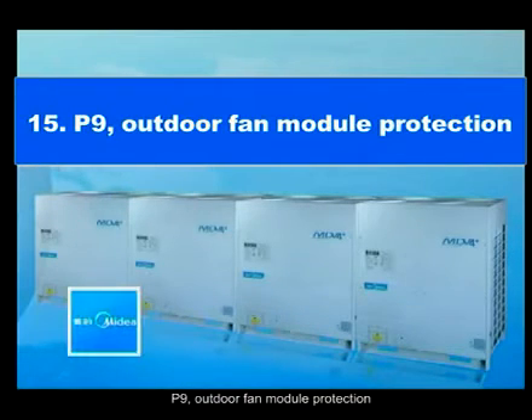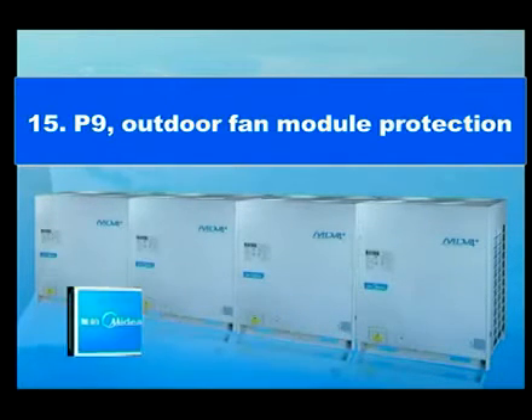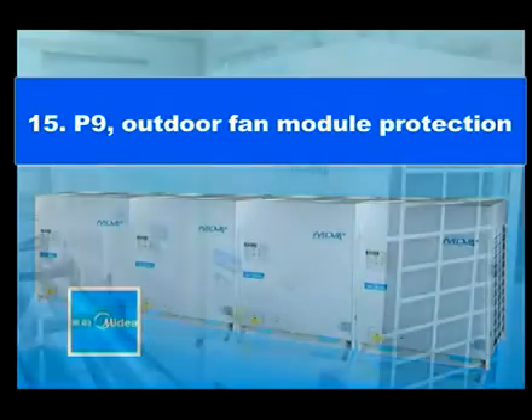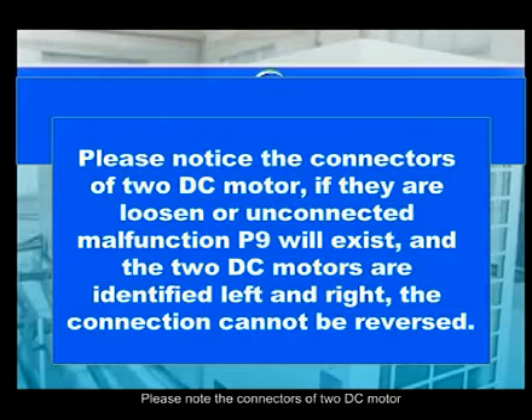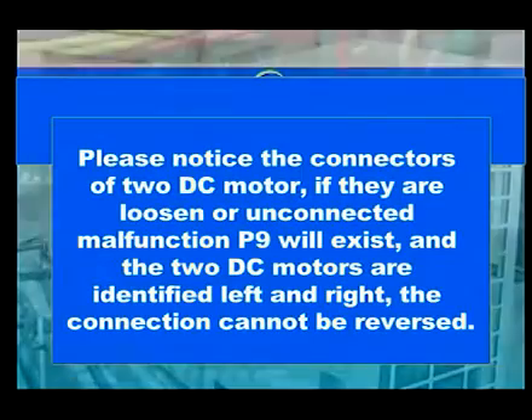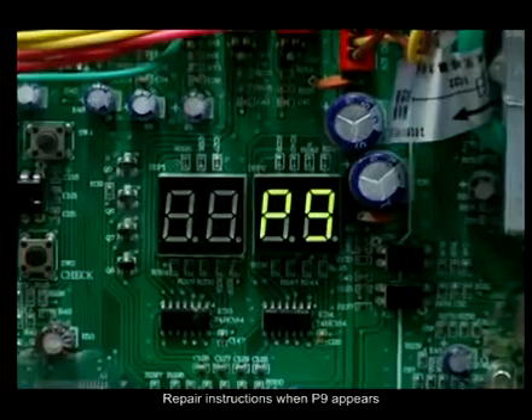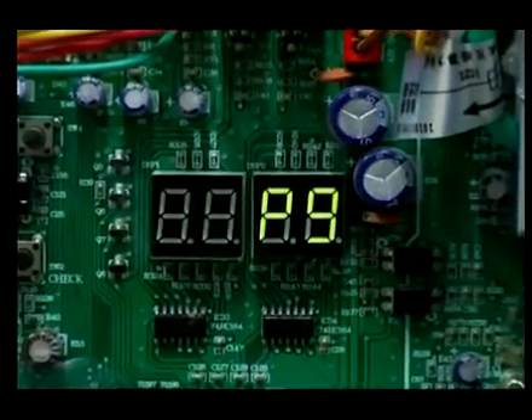P9. Outdoor fan module protection. Please note the connectors of the 2 DC motors. If they are loosened or unconnected, malfunction P9 will exist, and the two DC motors are identified as left and right. The connection cannot be reversed. Repair instructions when P9 appears.